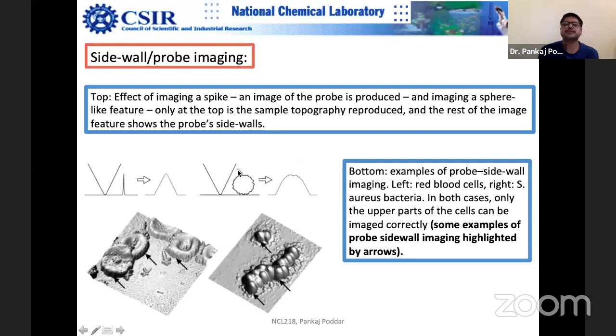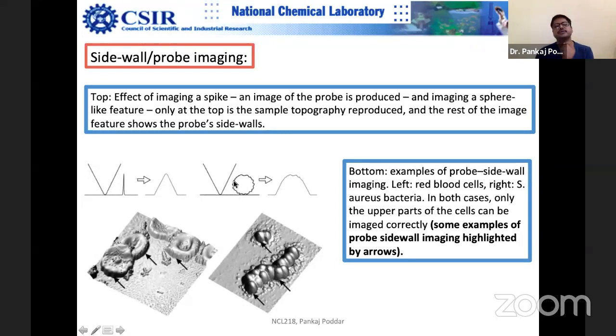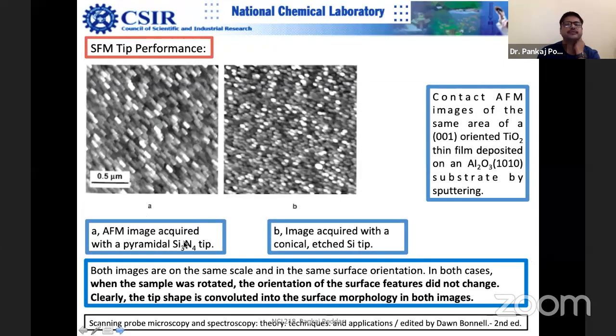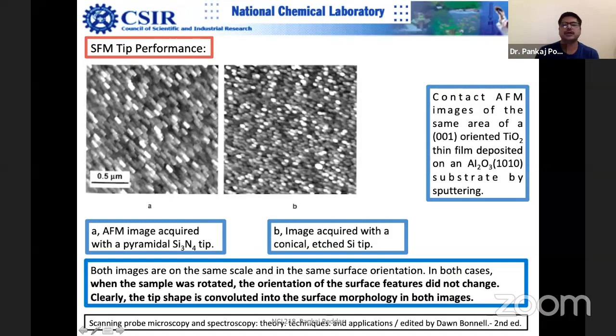Another example: for spherical particles, you can see that the sidewalls are broadened and the sphere doesn't look spherical. This AFM image was acquired with a pyramidal silicon nitride tip used in contact mode. Another image was acquired with a conical etched silicon tip used in tapping mode — this is the edge tip. You can do chemical etching in your own lab. There is a sharp difference between the two images.